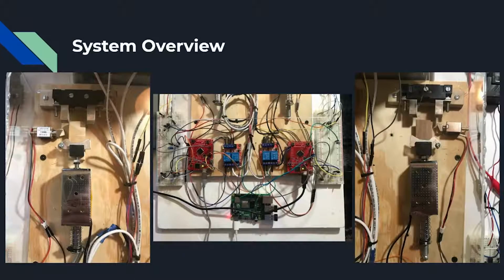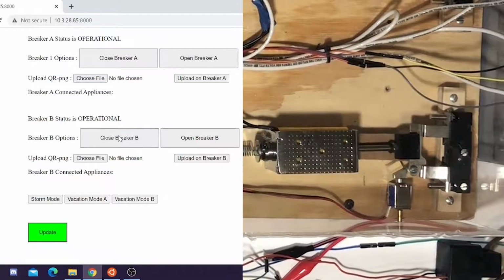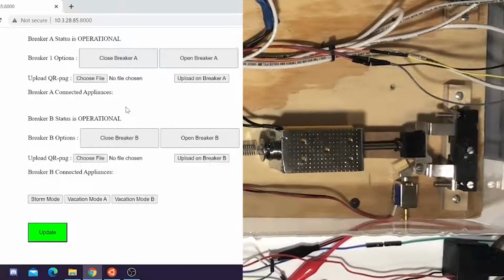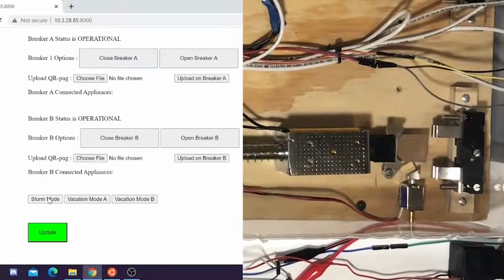These are more pictures of the actual build of the system. As can be seen, each component is connected as specified in the drawing shown in the previous slide. The breaker itself contains 2 solenoids: one acting as the main actuator that opens and closes, and another that is a latch that holds the breaker in place. The latch allows us to consume power only when opening or closing the breaker, eliminating heat dissipation and lowering our power consumption. The pull-up resistor is used to step up the 3.3 volt I/O of the TIVA to the 5 volts required to turn the relay on and off.